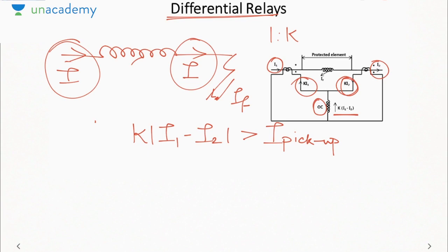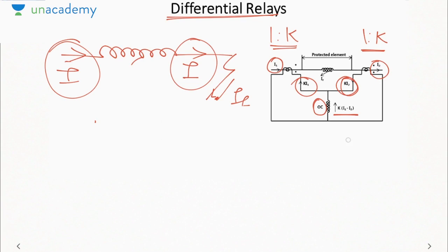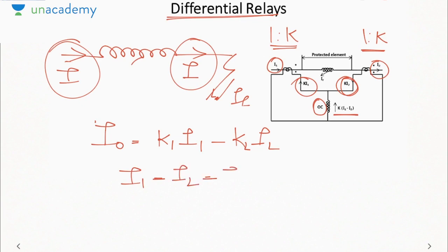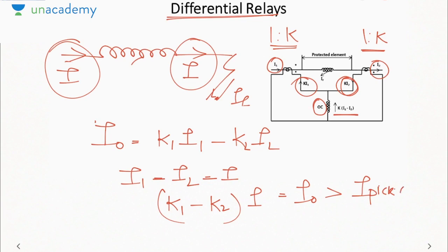The other thing is that here we will need identical current transformers, that is 1:k, 1:k. Otherwise, suppose one has a ratio K1 and the other has a ratio K2. Then the operating current will become K1 I1 minus K2 I2. Now suppose I1 and I2 are both equal, which means there is no fault. Then the operating current will become (K1 minus K2) into I. And if it is greater than the pickup current, the relay will operate. That means even if there is no fault, the relay will operate because there is a net current flowing through the operating coil of the relay. Why is it flowing? Because the transformation ratio of both the current transformers is not the same.